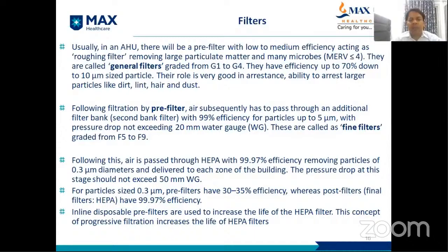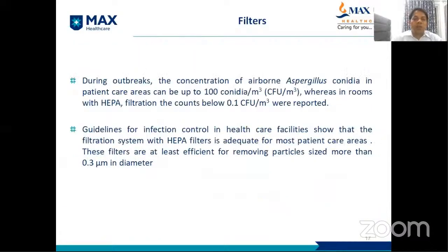Inline disposable pre-filters are used to increase the lifespan of HEPA filters. That means the pre-filter is also important. This concept of progressive filtration increases the lifespan of HEPA filters. During outbreaks, the concentration of airborne Aspergillus conidia can go to 100 conidia per cubic meter, whereas in rooms with HEPA filtration, 0.1 CFU per cubic meter has been reported.